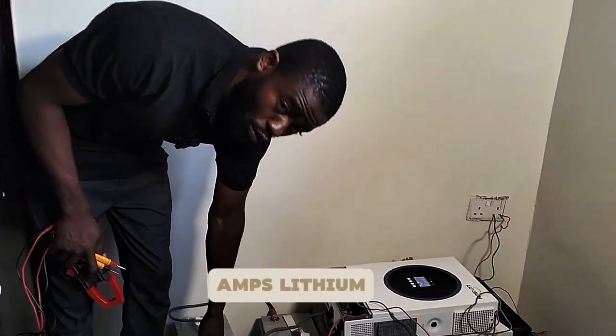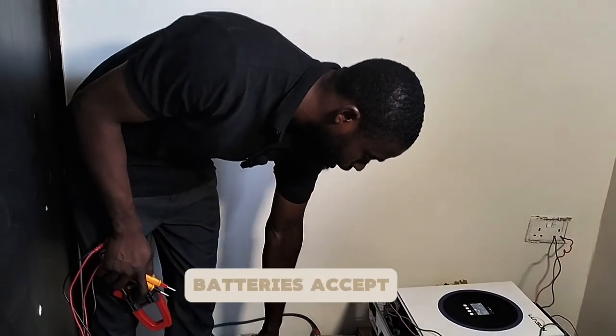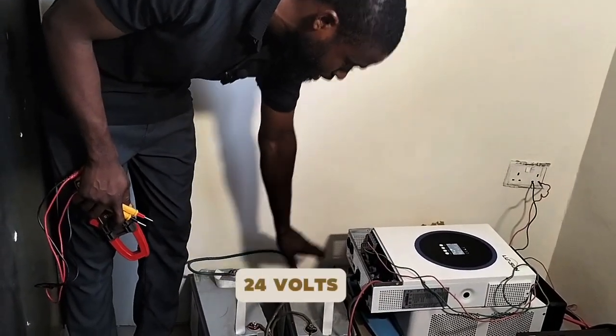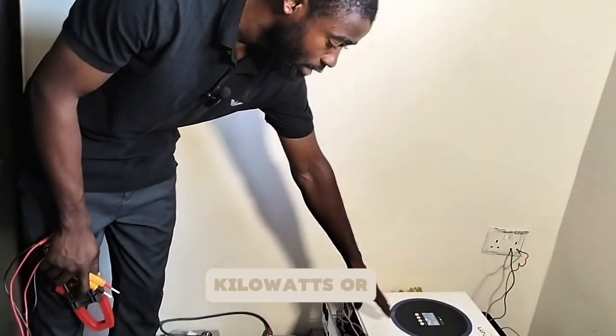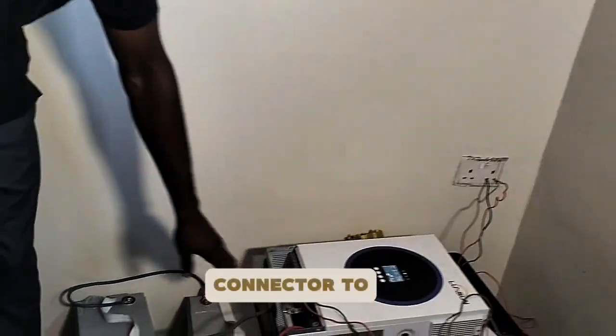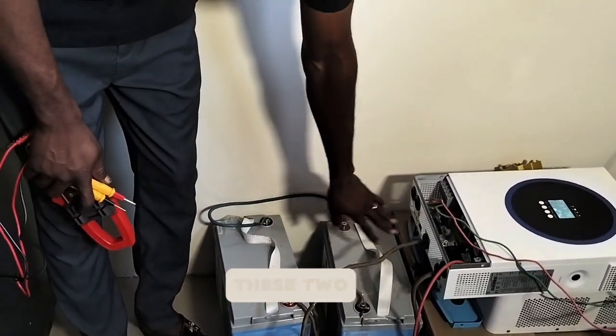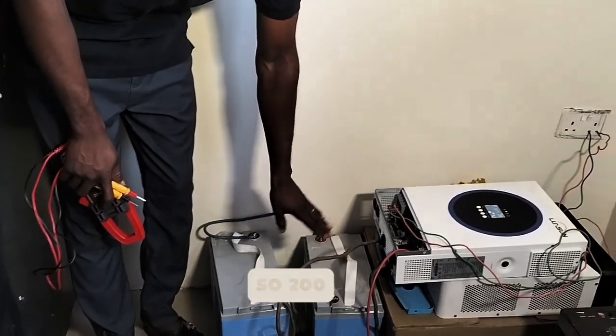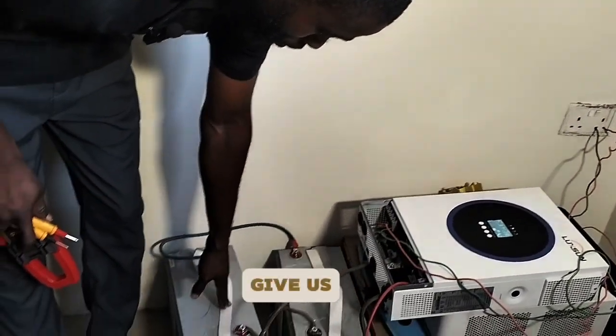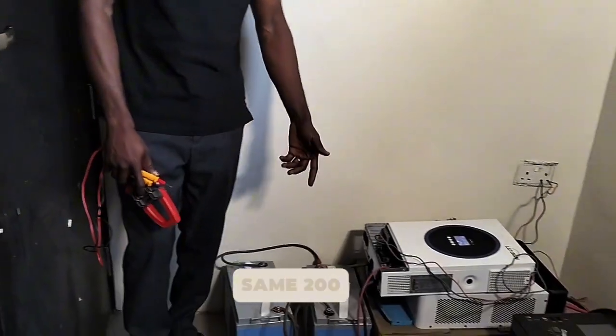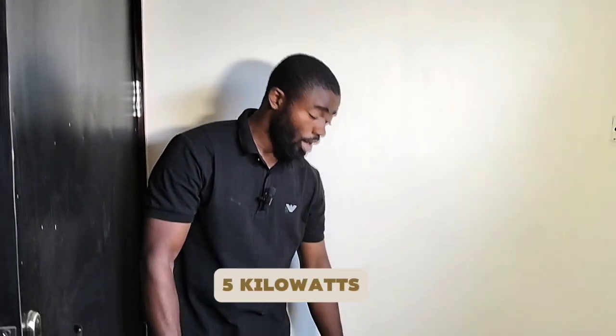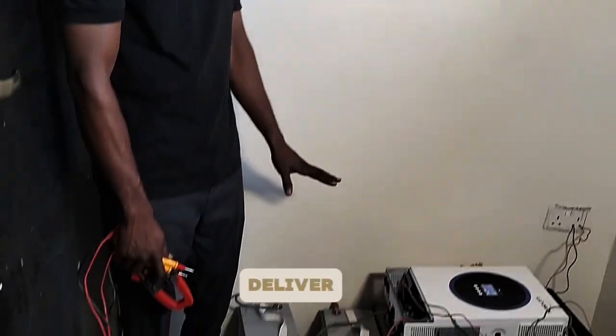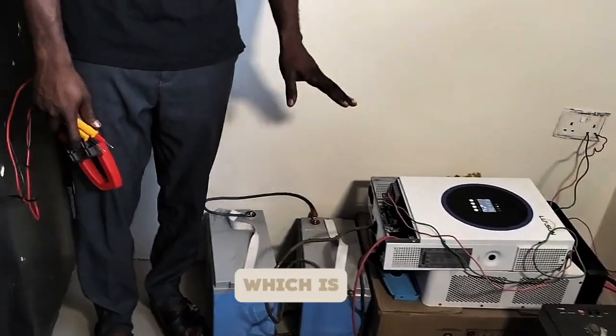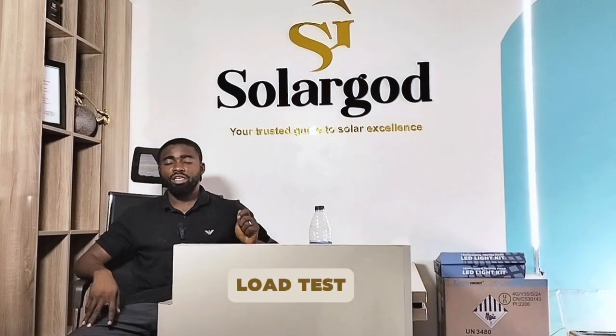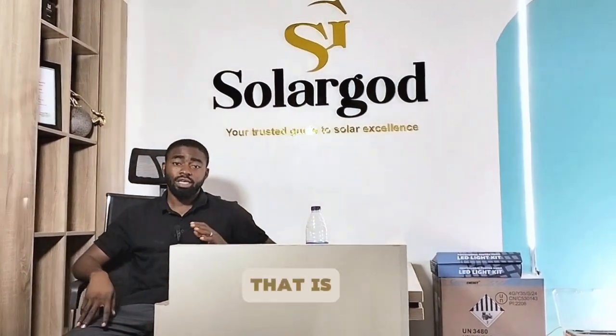This is a 200 amps lithium battery from Lemax, and the batteries accept series, because if you can see, this is a 24 volt inverter from Luxon, 3.2 kilowatts or 3.2 kVA connected to these two batteries. This inverter presently is working from these two batteries, and these two batteries are connected in series. So 200 amps plus 200 amps give us a total of 400 amps if connected in parallel. But connected in series, we have higher voltage with the same 200 amps, but in total we have 5 kilowatt hour, and the battery has been able to deliver up to what is stated on the manual, which is 80% depth of discharge. From our load test, the Lemax 200 amps lithium battery has proven that it's very reliable.